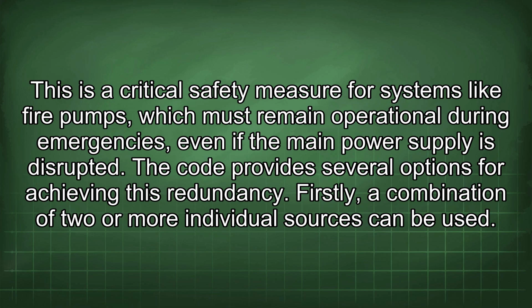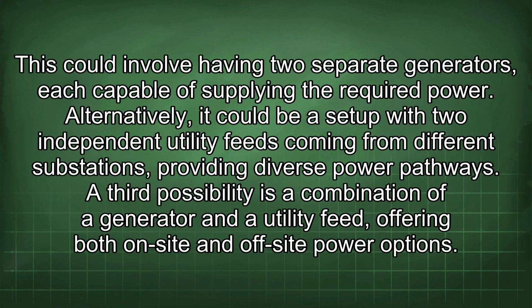The code provides several options for achieving this redundancy. Firstly, a combination of two or more individual sources can be used. This could involve having two separate generators, each capable of supplying the required power. Alternatively, it could be a setup with two independent utility feeds coming from different substations, providing diverse power pathways. A third possibility is a combination of a generator and a utility feed, offering both on-site and off-site power options.